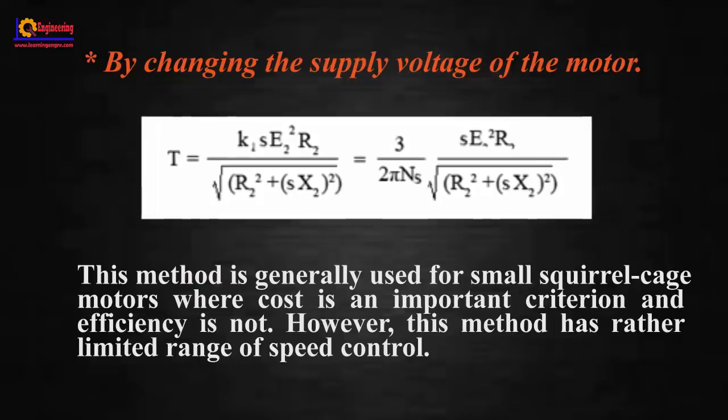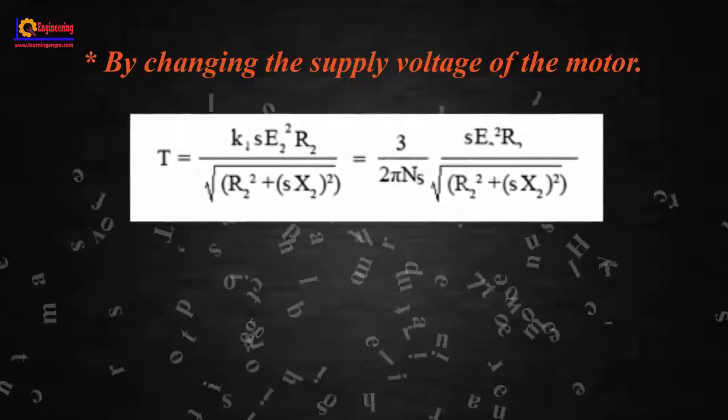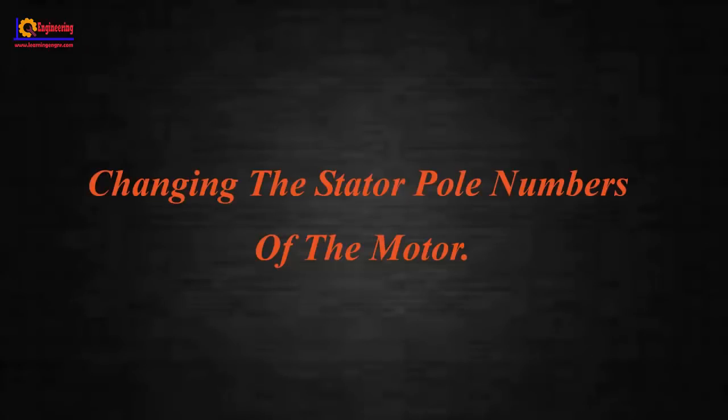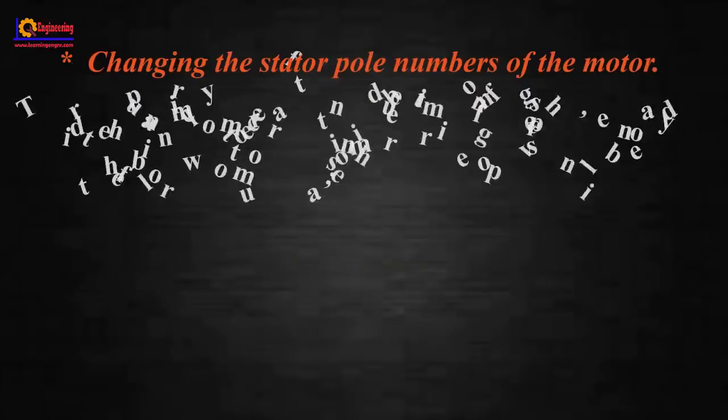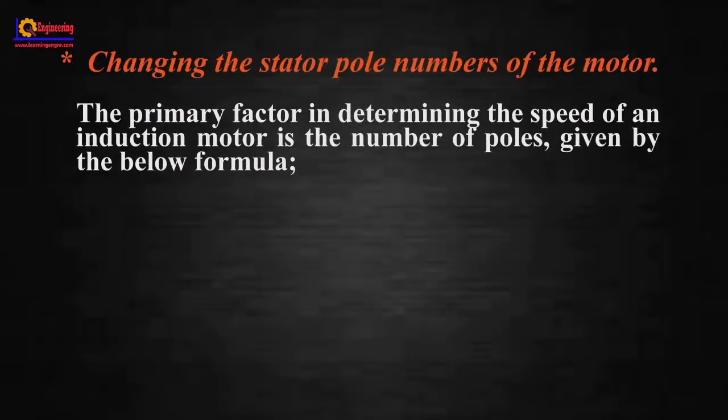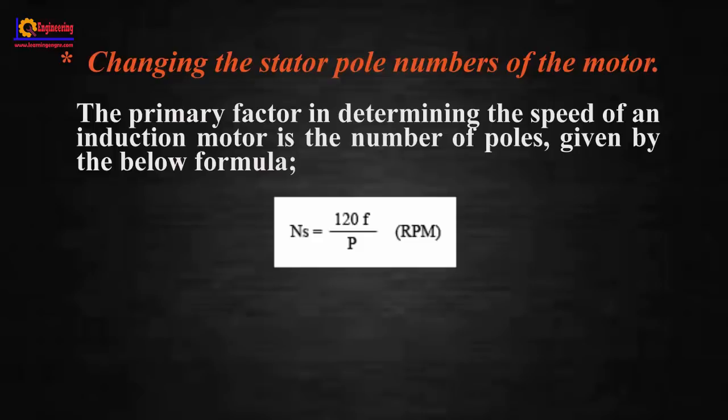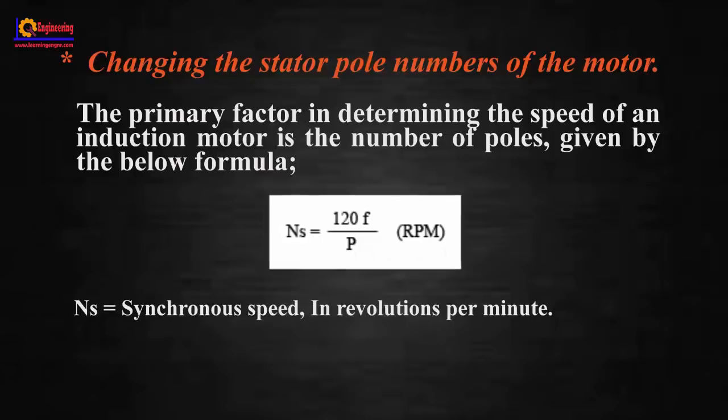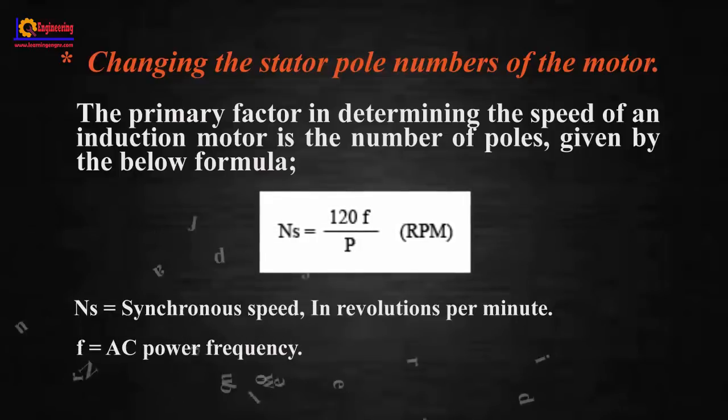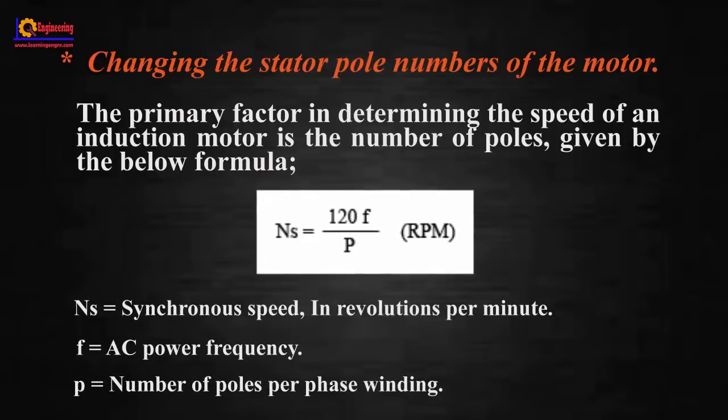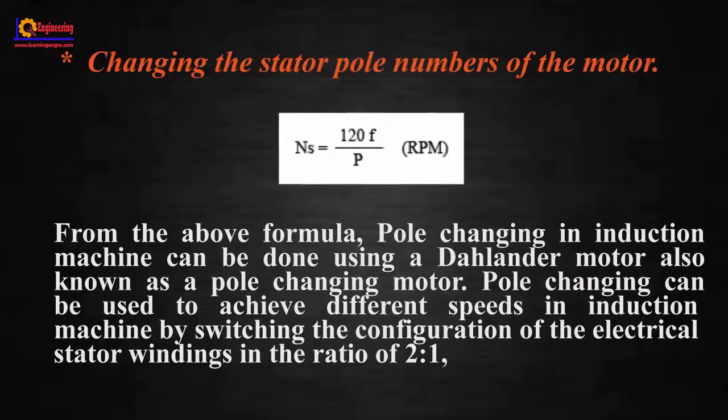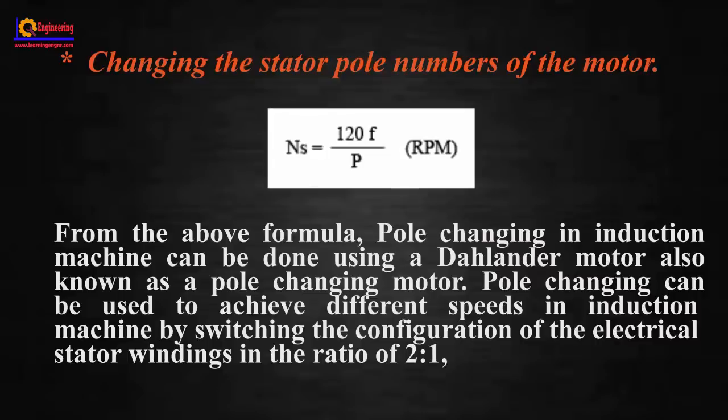Changing the stator pole numbers: the primary factor in determining the speed of an induction motor is the number of poles, given by the formula Ns = 120f/P (RPM), where Ns is synchronous speed in revolutions per minute, f is AC power frequency, and P is number of poles per phase winding. Pole changing in induction machine can be done using a Dahlander motor, also known as a pole changing motor.